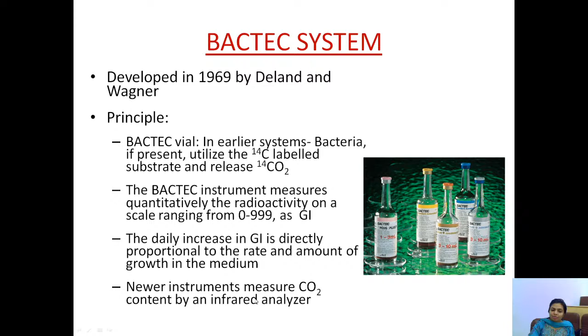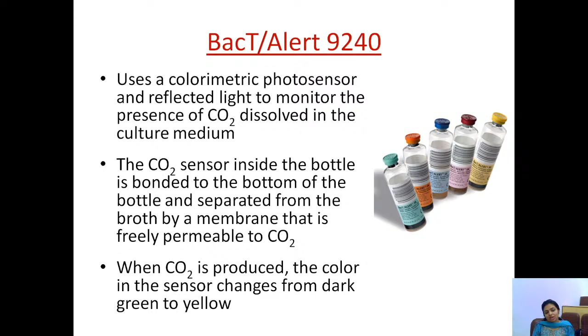This is the BacT/Alert 3D. It uses a colorimetric sensor and reflected light to monitor the presence of CO2 dissolved in the culture media. Whenever an organism is present in the sample, it uses the carbon source and releases carbon dioxide. So how do we detect this carbon dioxide? This is the basis of this automation. The CO2 sensor inside the bottle is bonded to the bottom of the bottle and separated from the broth by a membrane that is freely permeable to carbon dioxide. Whenever carbon dioxide is produced, the color of the sensor changes from dark green to yellow.